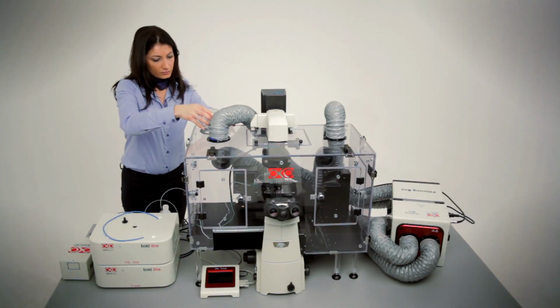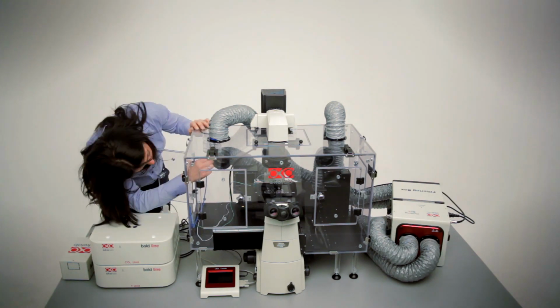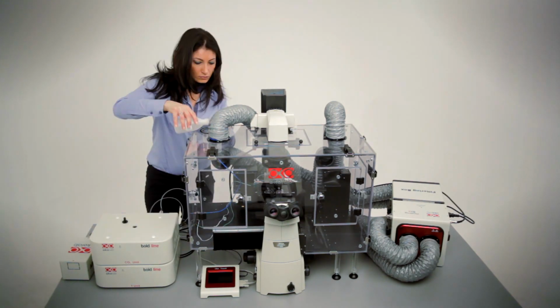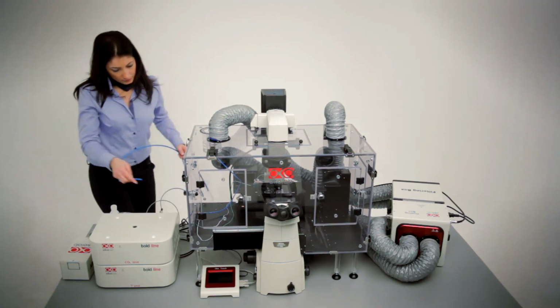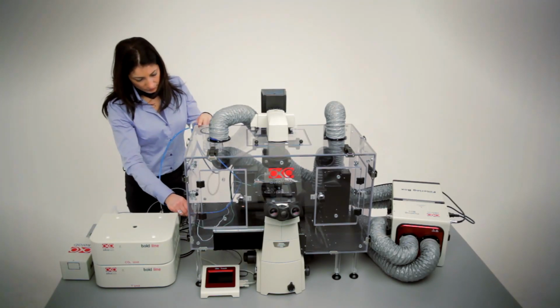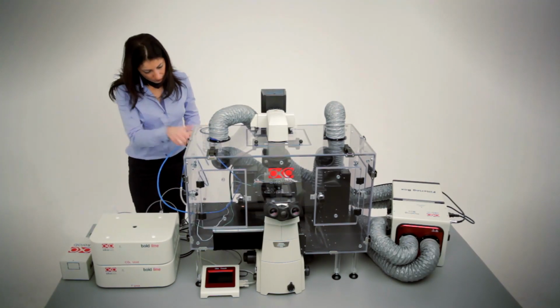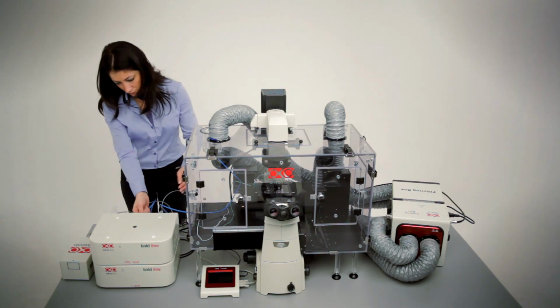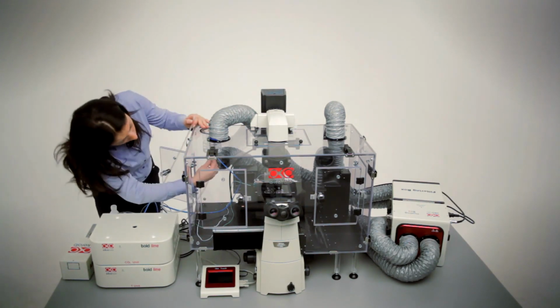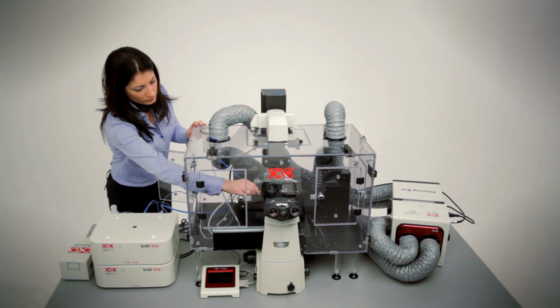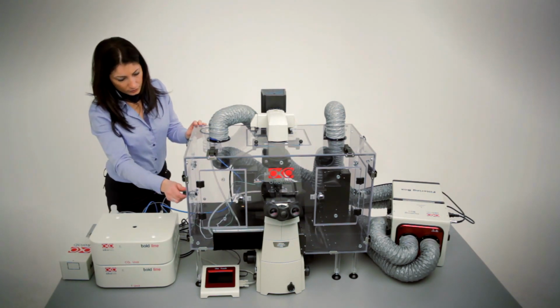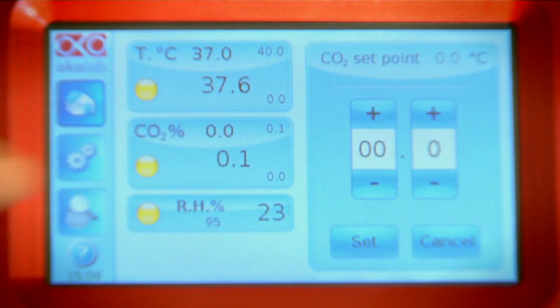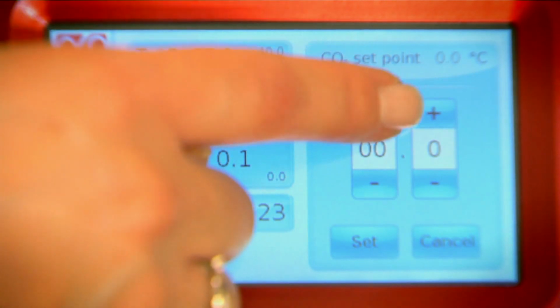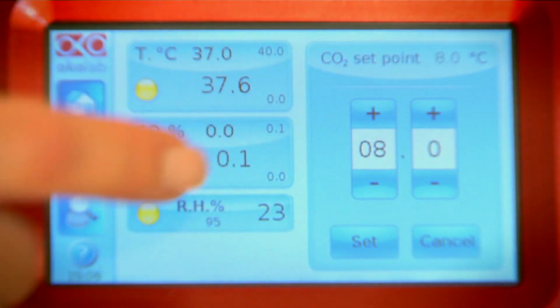Assemble the vibration-free humidity module and fill the glass reservoir with distilled water. The pre-assembled blue tube should be used to connect the gas controller to the vibration-free humidity module. Use the flexible silicone tube to connect the humidity module to the gas chamber. The desired gas concentration and total output flow rate are set via touchpad.